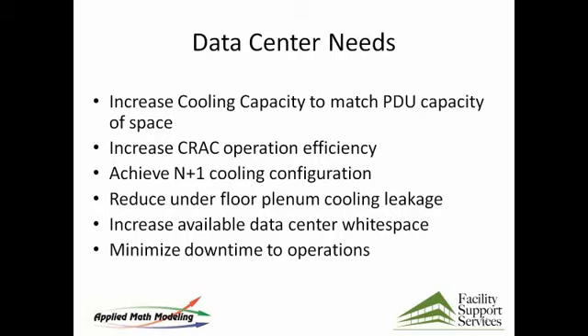So I took another shot of your first pass here. Want to walk us through this a little bit here? You got cold aisle down the middle, right? That's correct. So cold aisle down the center of the room. All the racks have been moved in to where there's no spacing between them. All the racks have been turned properly so that their intakes all match and all the exhausts match. And we blocked off the underfloor plenum on this model. Now, you've got some front to tops here as well, front to rear and front to tops.